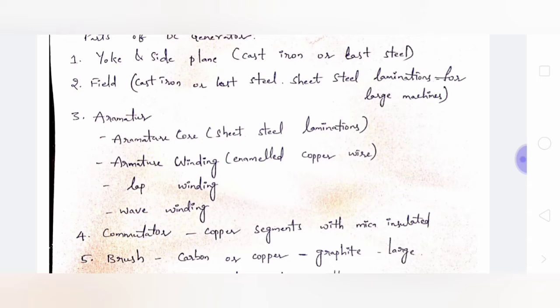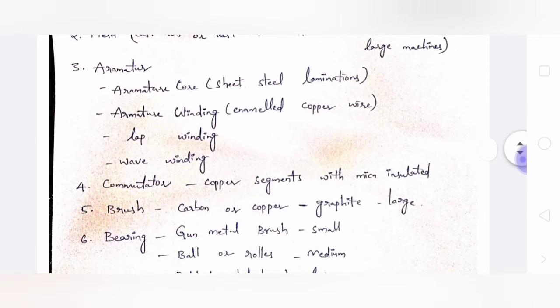The field is the stator and the armature is the rotor. The armature core is made up of silicon steel lamination. Armature winding uses enameled copper wire. There are two types of winding: lap winding and wave winding. In lap winding, the total winding is divided into parallel paths equal to the number of poles — two poles gives two paths, four poles gives four paths. In wave winding, there are always two parallel paths.